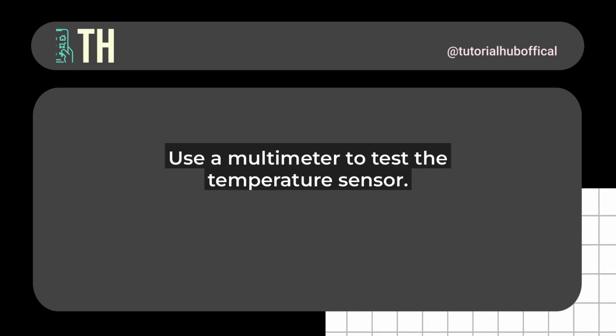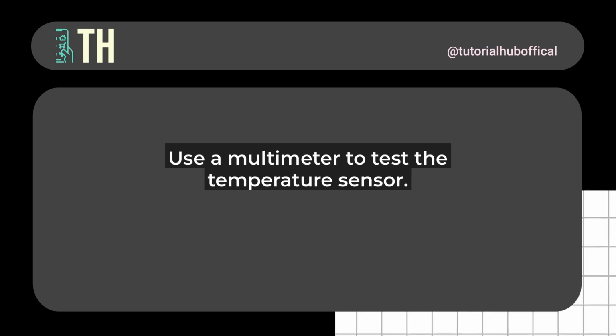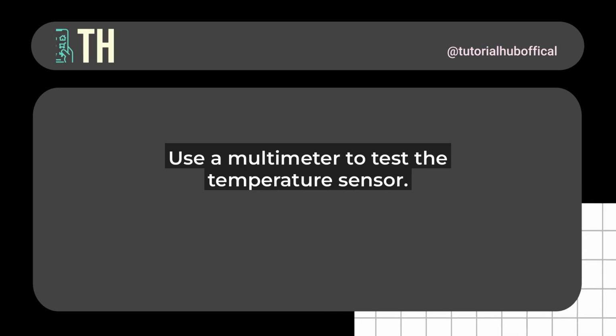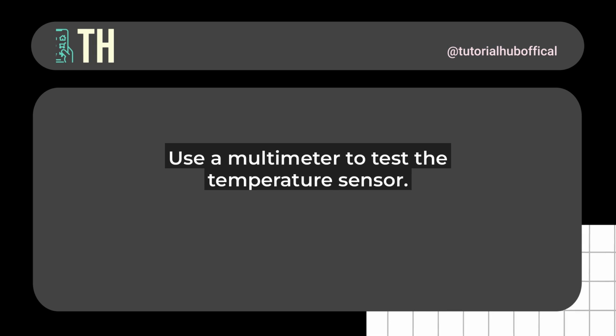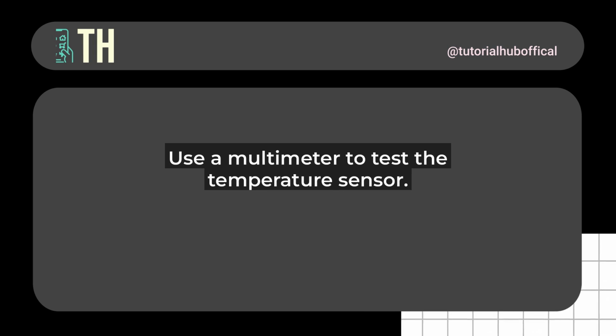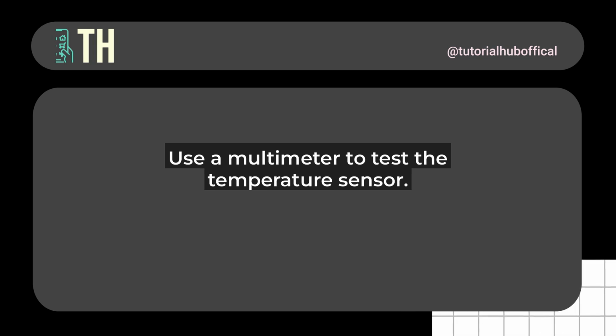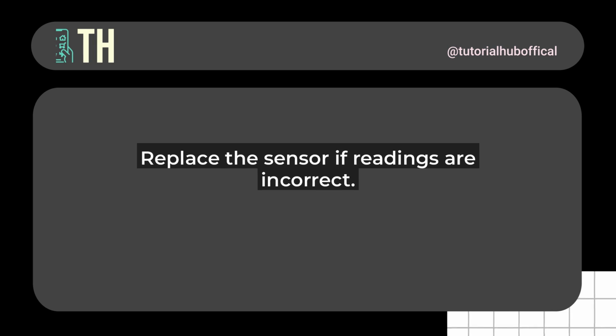If the F30 error persists, you might need to test the temperature sensor itself. This involves using a multimeter to check for continuity. Don't worry, I'll walk you through it. Set your multimeter to the ohms setting and touch the probes to the sensor's terminals. A reading between 1000 and 1100 ohms at room temperature is normal. If it's way off, the sensor is likely faulty and needs replacement.